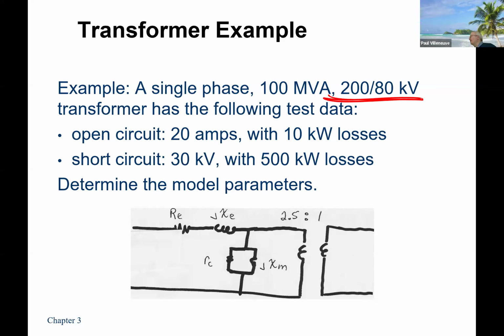Same thing with a short circuit test. I didn't tell you the current because you should be able to calculate it based on the nameplate of the transformer. 100 MVA, sorry, and the voltages are 200/80 kV. It does matter. Use the convention that we talked about. So you do have the ability to get V open circuit, and you do have the ability to get I short circuit, or V full load and I load loss.